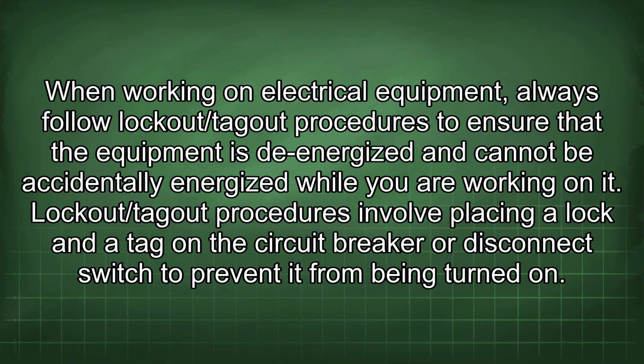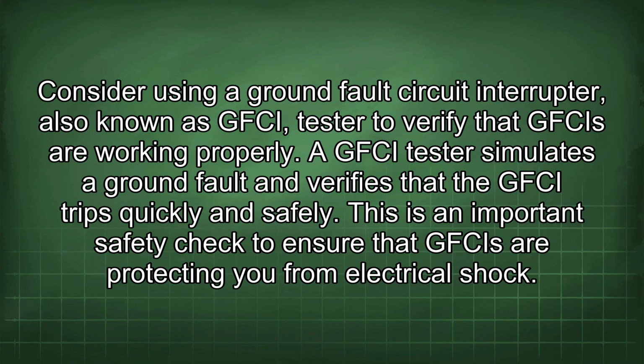being turned on. Consider using a ground fault circuit interrupter, also known as GFCI, tester to verify that GFCIs are working properly. A GFCI tester simulates a ground fault and verifies that the GFCI trips quickly and safely. This is an important safety check to ensure that GFCIs are protecting you from electrical shock.